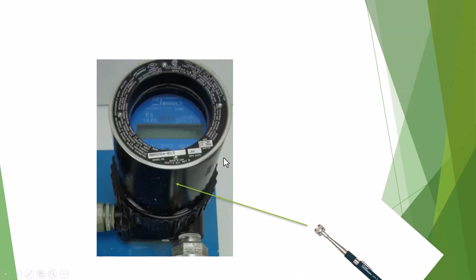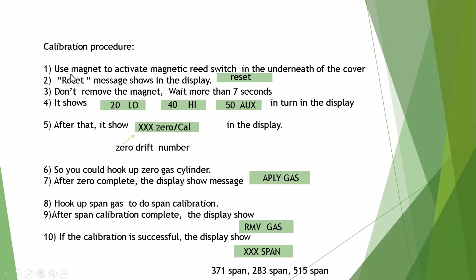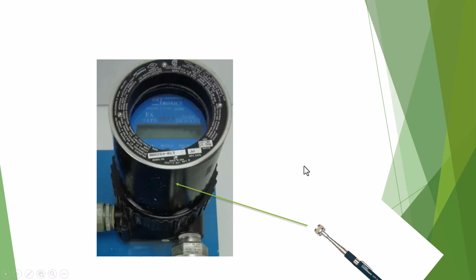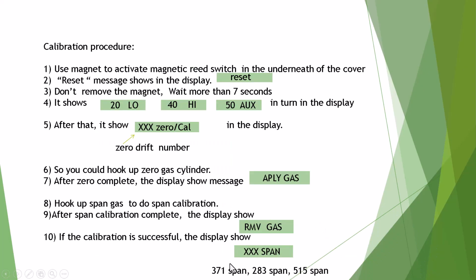So if you want to calibrate, you have to use a magnet. It's underneath the cover in here. So I'll show you how to calibrate. Use the magnet to activate the magnetic reed switch underneath the cover. The reset message will be displayed here. So if the reset message comes out, you don't remove the magnet, just keep the magnet touched to the cover for more than 7 seconds. After more than 7 seconds, it shows 20 LO, 40 HI, 50 AUX, in turn on the display.